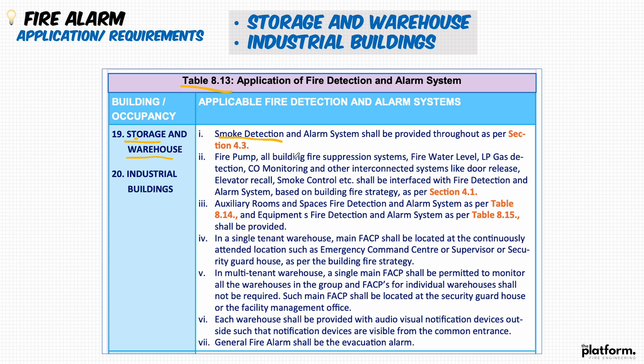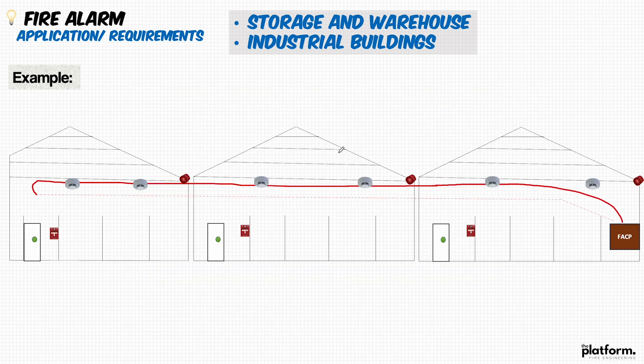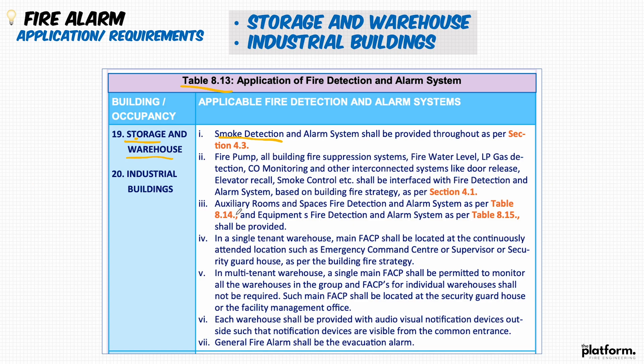If you have a fire pump, building fire suppression system, fire water, or any other system, it shall be interfaced with the fire detection system. The code mentions interfacing with the fire alarm system and other third-party and fire protection systems. I did not add any interfacing module in this layout because I don't know what is installed there, but you need to know — if you have a lift, a pump, an extract fan, or any other system that needs to be connected and integrated with the fire alarm system, then you will add interfacing devices to the loop.